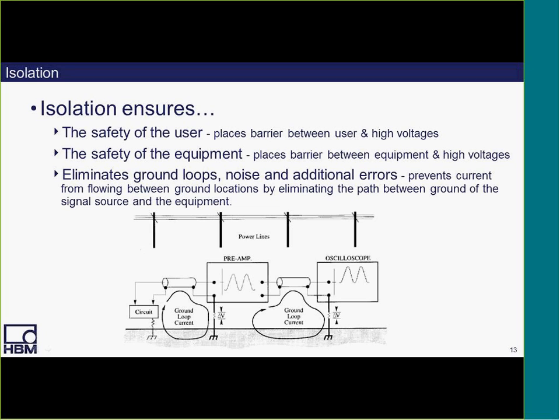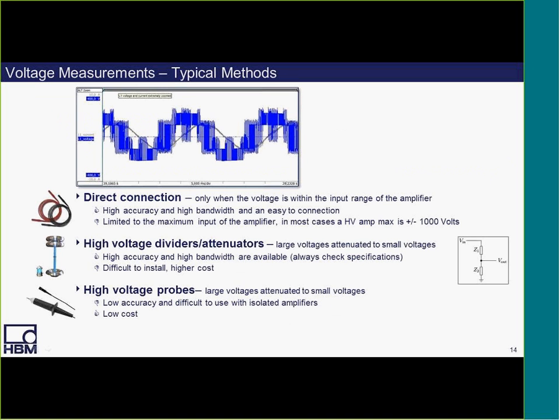The equipment is going to be placed, basically the safety of the equipment is a barrier between the equipment and the high voltage due to the isolation, which will also eliminate ground loops, noise, and additional errors, which will prevent current from flowing between ground locations by eliminating the path between ground of the signal source and the equipment. And we'll talk more about isolation in each of the different power applications in just a moment.